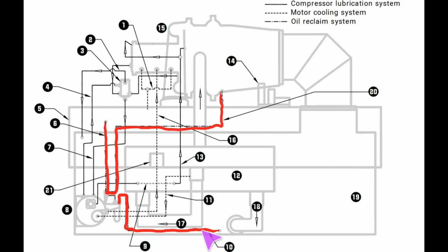This is a very common issue that a lot of people deal with. I've come up on several machines where this second stage line has a ball valve on it many times, or a service valve of some sort, and it will be closed. So you have to be very careful of that and mindful of it, and you don't want to just start pumping oil into these machines. Depending on the load conditions, it's very common for the oil to have migration issues on these. And when that happens, that oil had to have gone somewhere. If you don't see it sitting on the ground in front of you, it's somewhere in the system. So we need to do our best, whether it's getting a high enough load on the machine or making sure that the return lines are all open properly, something to attract that oil back into that tank.